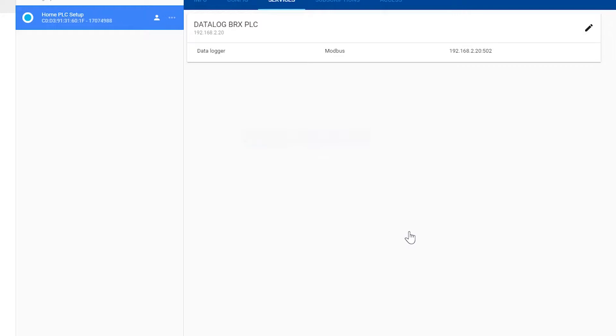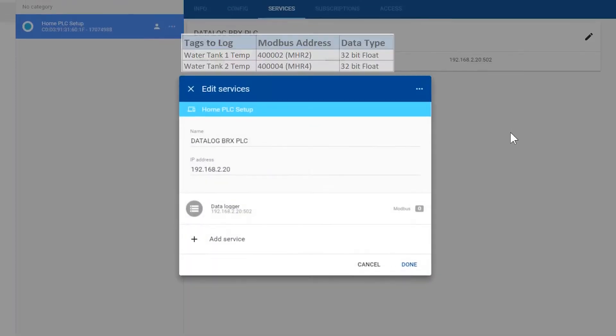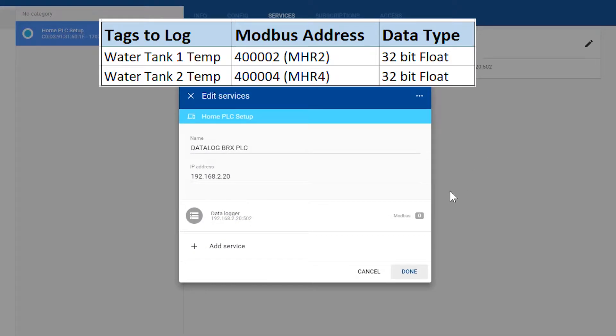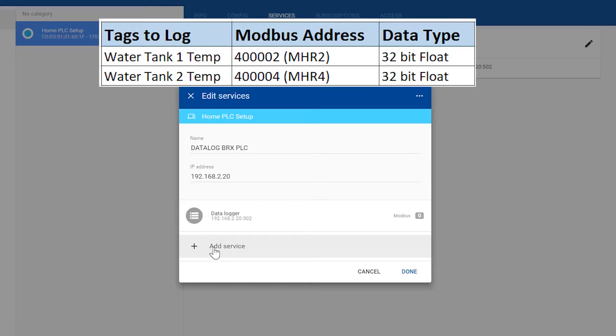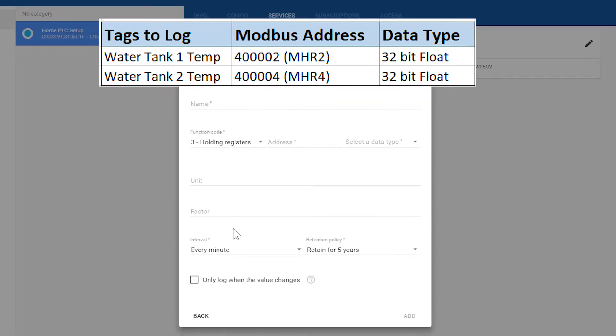Now that we have created the device and applied the service, we need to edit the device to add the individual tags. I am going to log two tags from my Do-more BRX PLC that I have already set up. Both tags are 32-bit floating points mapped to Modbus addresses 400002 and 400004. These tags are both temperatures of a water tank, so I will name the first tag as follows.